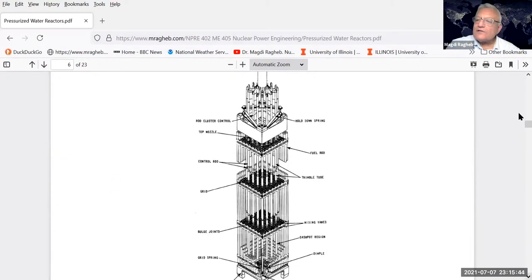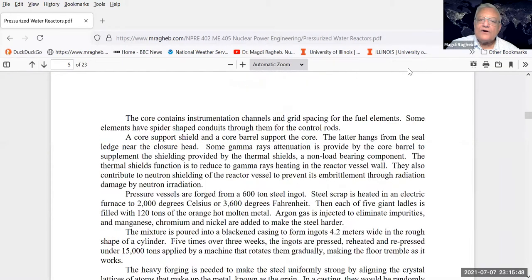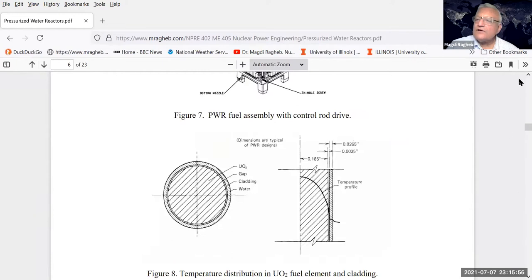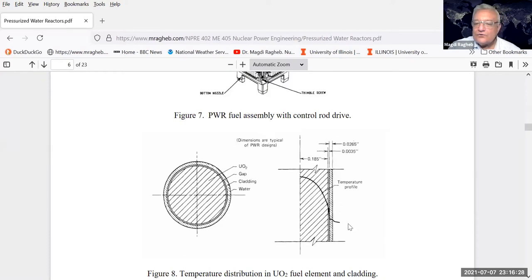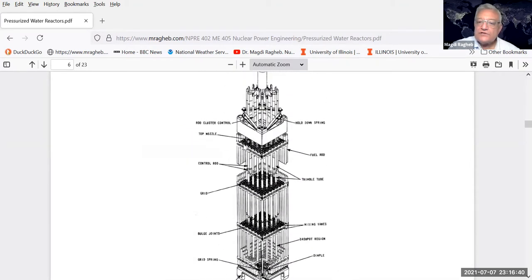This is a typical fuel element. Notice we have square channels - each one contains a fuel assembly. The fuel inside the core is pellets of uranium dioxide surrounded by a cladding. The fuel is UO2. There is a gap filled with helium as a thermal bonding between the cladding and the fuel. The temperature peaks near the center and then comes down through the gap of helium, through the cladding - the British call it the can, in the United States we call it the cladding.